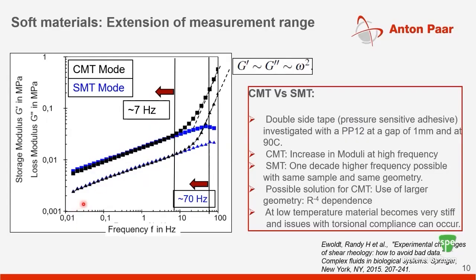several hundreds of pascals. And typically people in this industry, they do a lot of frequency sweeps. They're heavily used in the PSA industry. And here I am showing you some data of a frequency sweep measurement on a PSA type. It's a double-sided tape, which was investigated with a parallel plate type geometry. Now, this was done on the multi-drive device where you can see data from both the CMT and SMT mode, right, which we talked about earlier.